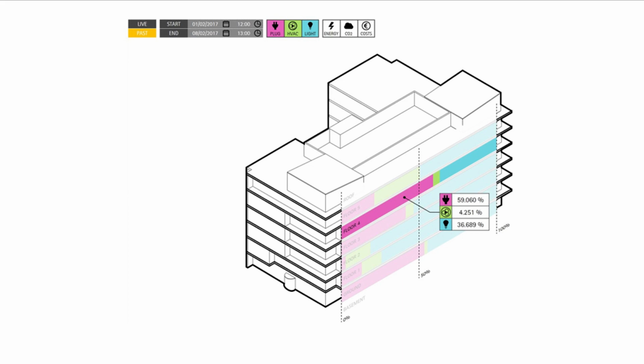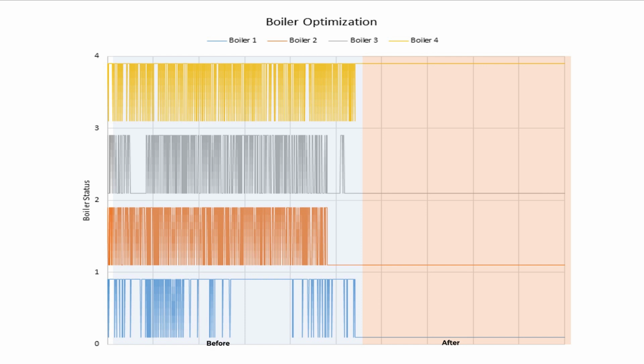Where the actual engineering comes into this, that a BMS would never pick up, is here we're looking at the on-off statuses, where off is at the bottom and on is at the top, for 4 different boilers. The goal here, for this retrofit building, was to meet the winter set point. But if you were to sit and actually do the engineering calcs on it, then one boiler has perfectly sufficient capacity to meet set point. You'd obviously not want to stress a boiler that hard, so perhaps you'd have 2.